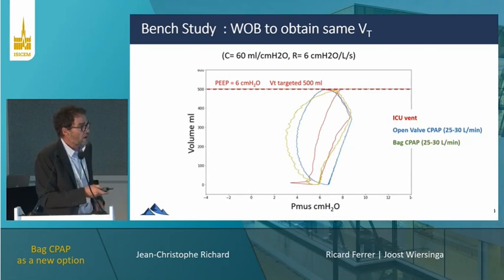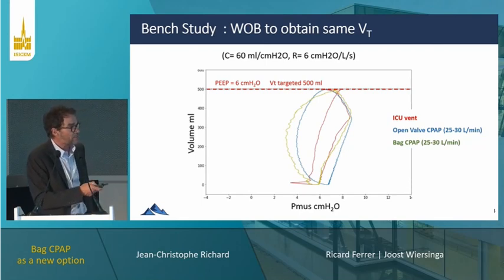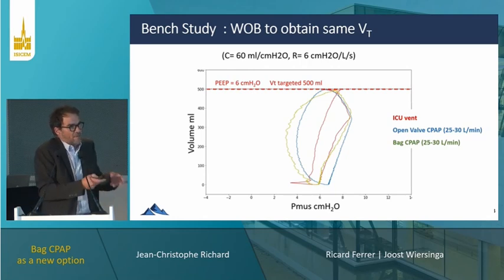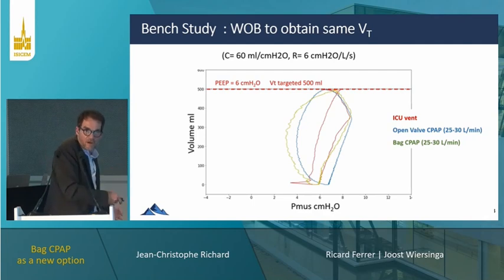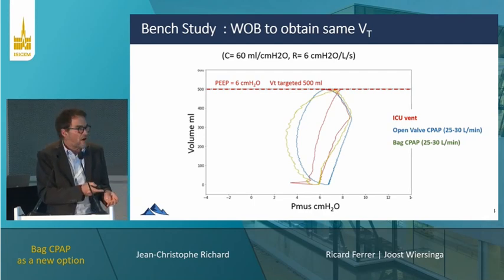bad. So we compare the different systems using this pressure-volume curve, a current way to assess work of breathing. The red loops are obtained with the ICU ventilator, which is the gold standard. You can see inspiration, expiration. And as you can see, with the bag CPAP or the open valve, the work is a little bit, but significantly, higher compared to the ventilator.